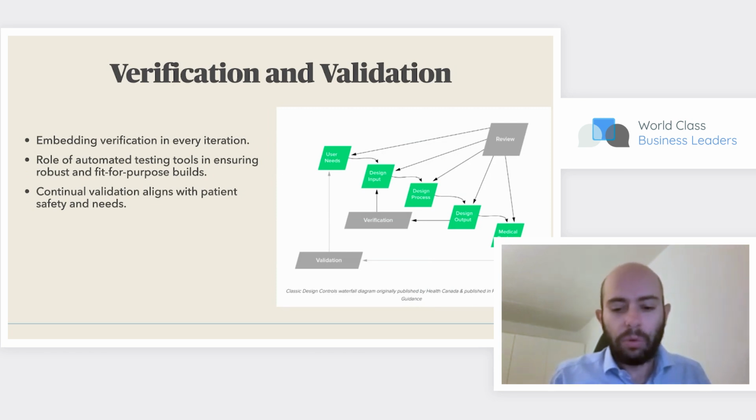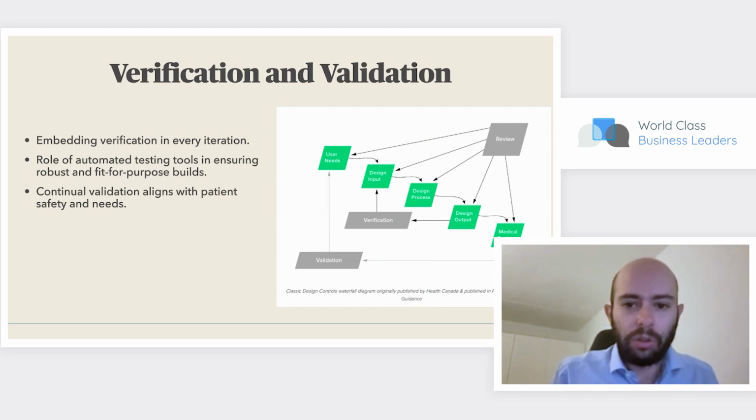And after you want to cut a release, then you validate, meaning that you bring in patients, you perform your summative studies, and you demonstrate the effectiveness and the safety of your device. You document it, and then you present it to the regulators to approve it.